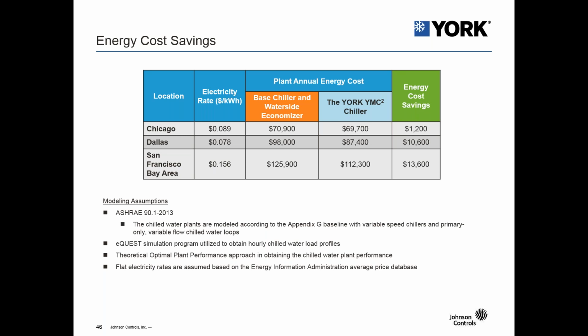So when we look at the plant annual energy costs, you'll see the energy costs for the base chiller and water side economizer in orange. In Chicago, the total operating costs were just over $70,000, 98 in Dallas, and 125 in the San Francisco Bay Area. And that system, utilizing a base chiller meeting the ASHRAE 90.1 requirements with a water side economizer, was then compared to a York YMC squared chiller without a water side economizer.